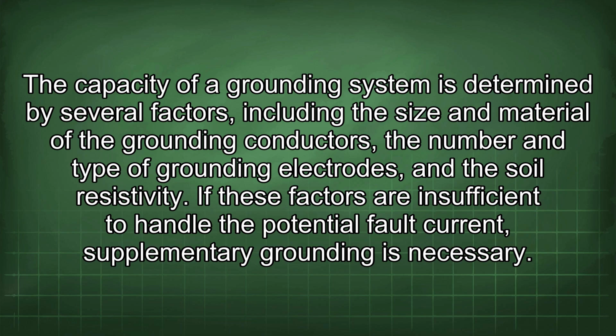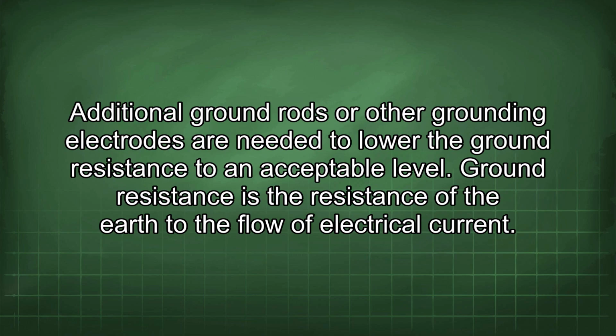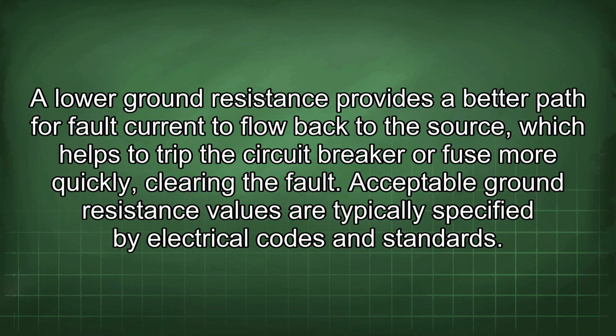If these factors are insufficient to handle the potential fault current, supplementary grounding is necessary. Additional ground rods or other grounding electrodes are needed to lower the ground resistance to an acceptable level. Ground resistance is the resistance of the earth to the flow of electrical current. A lower ground resistance provides a better path for fault current to flow back to the source, which helps to trip the circuit breaker or fuse more quickly, clearing the fault.